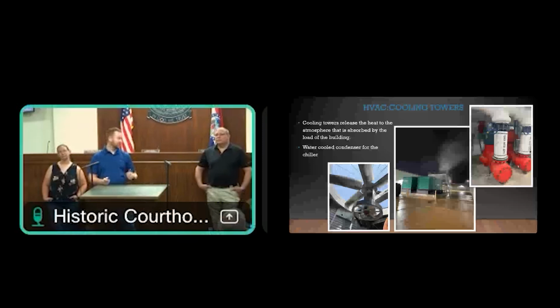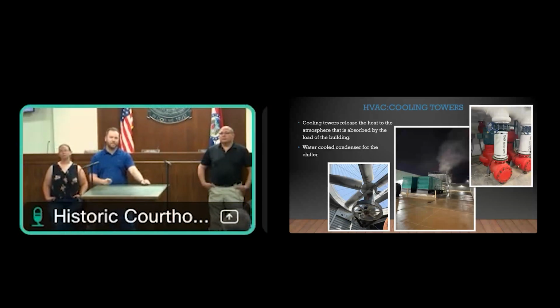As Franz was talking about earlier, our cooling towers, there's another picture of the fan. It's probably about 10 to 12 feet across, and there are two of them. The cooling tower has two cells sitting side by side, so there are two fans that big. This is the piece of equipment that releases the heat load that the chiller picks up from the building and puts it outside. On the right, the pumps are about 6 feet tall, and they do all the pumping for the cooling tower. That middle picture is after our recent storm, when the chillers started back up again and there was a heavy heat load, so you can see that going out the top of the cooling tower.